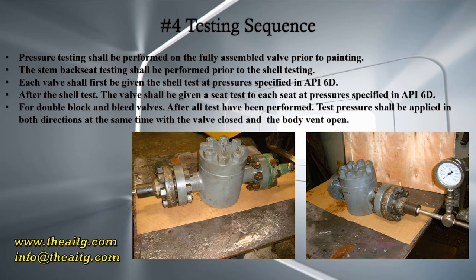For double block and bleed valves, after all tests have been performed, test pressures shall be applied in both directions at the same time with the valve closed and the body vent open. In this photo you can see a valve being tested with blind flanges performing a shell test. In this photo they are performing a seat test.